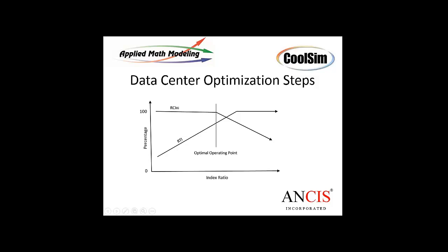And then as you start to turn down the air handlers, the flow coming into the room, you'll start to climb the RTI curve. It'll go up, and at some point you'll hit an inflection where RCI high begins to decline. That point where it starts to decline is a result of the fact that in this scenario we don't have perfect air management.